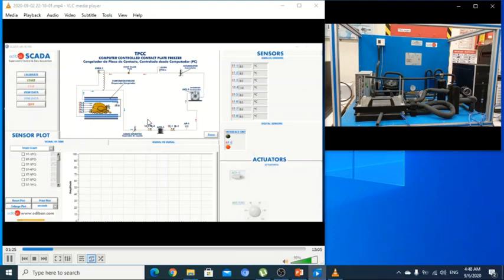Here this is at the suction, and ST8 is attached to the contact plate, and it will provide you the temperature at the evaporator, I mean, at which temperature the evaporation is going on.